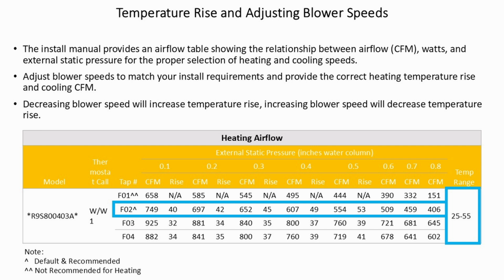See the heating airflow correlation on the chart below, showing the effect that external static pressure has on the CFM and the temperature rise at the default fan speed. Heating temperature rise range should be 25 to 55 degrees Fahrenheit.